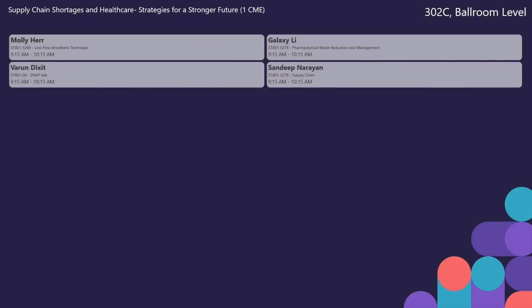And sometimes I notice 20, 30 minutes goes by as I'm lining up the patient, checking blood. And in some cases, people just forget altogether. I do appreciate the fresh gas flow warnings, but have we tried to do anything with industry to target some of these practices? It seems like it would be a simple programming thing. If I want to go down to 1 liter, okay, reduce your flow, and then when it's practical to do so, reduce it further, as opposed to a hard stop. Have you guys had any kind of interactions with industry for that?